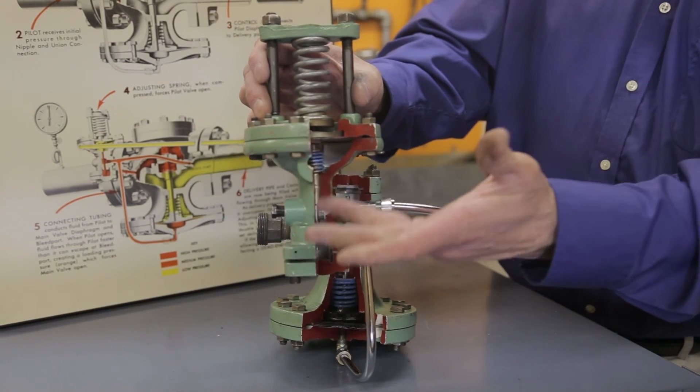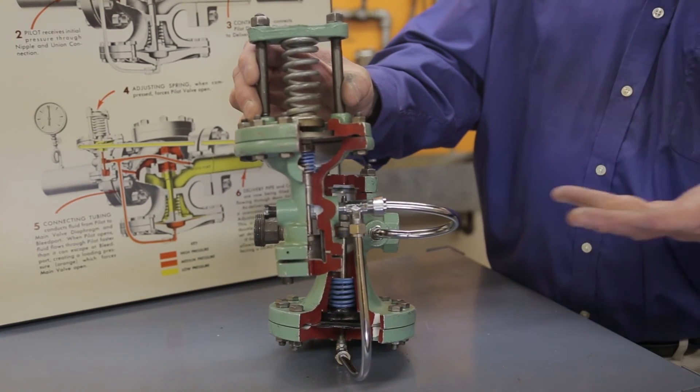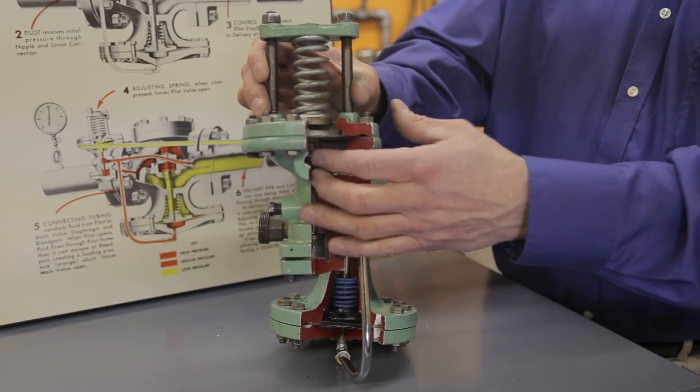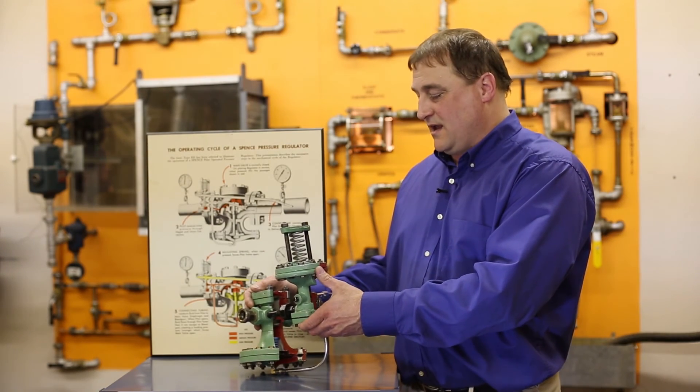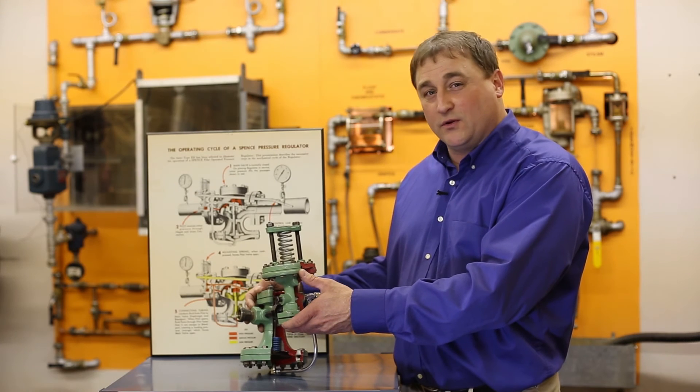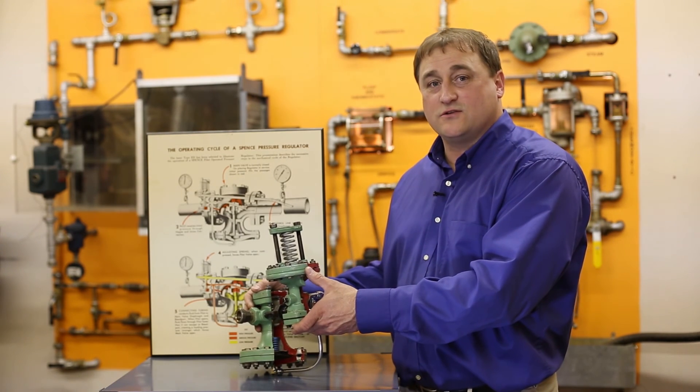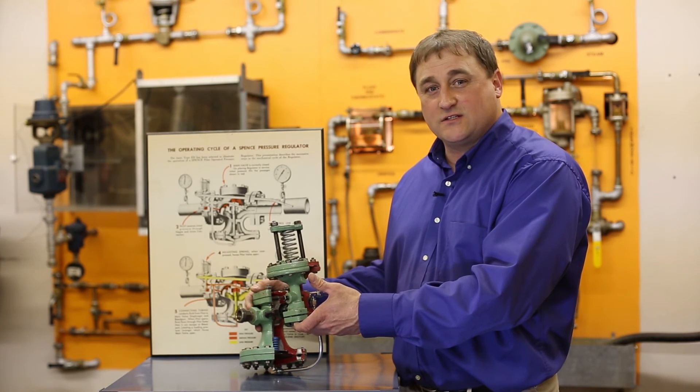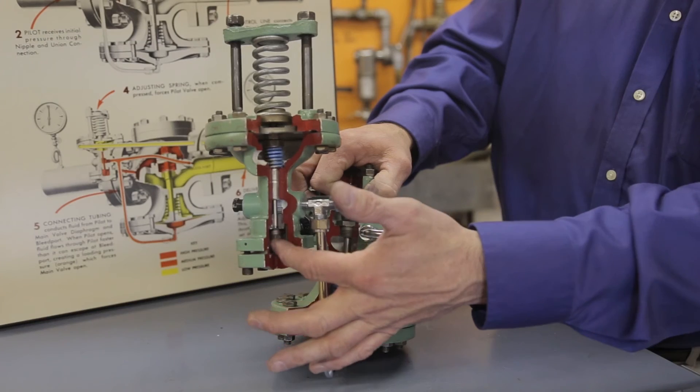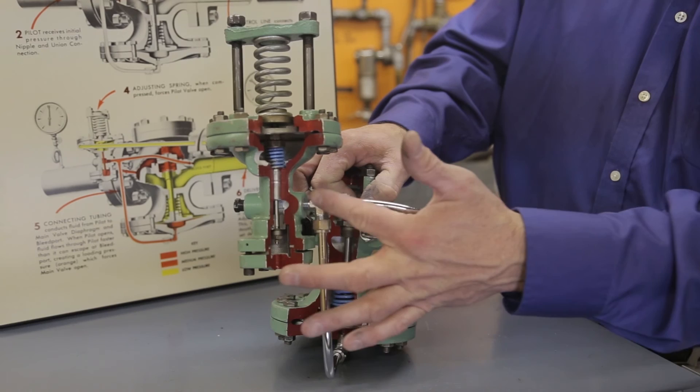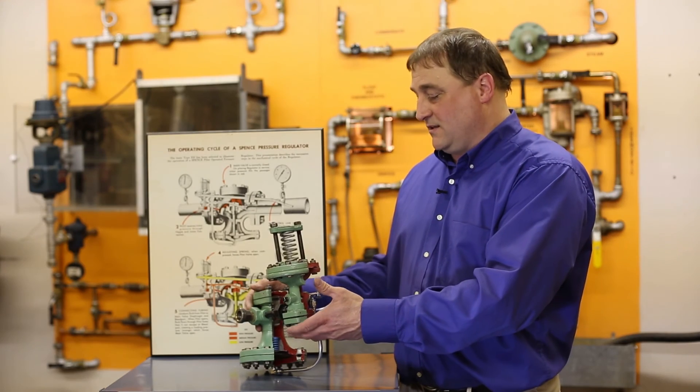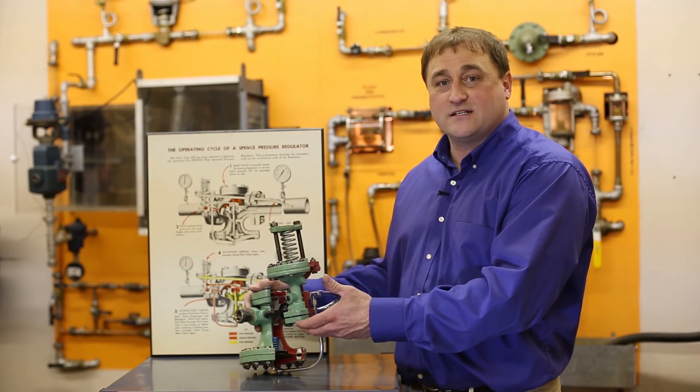Where would a pilot-operated pressure-reducing valve be used? Typically, we see these applications on steam, for example, where we want to run things like building automation, HVAC units, shell and tube heat exchangers, low-pressure steam applications such as humidification, and basically your building heating demands that utilize low-pressure steam.